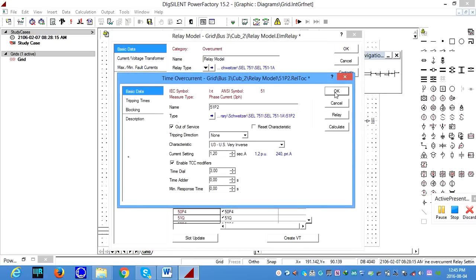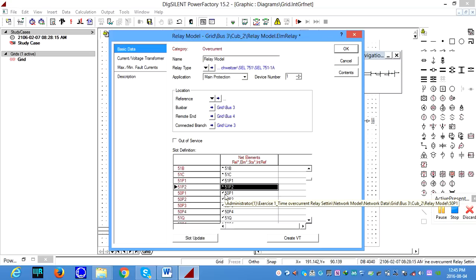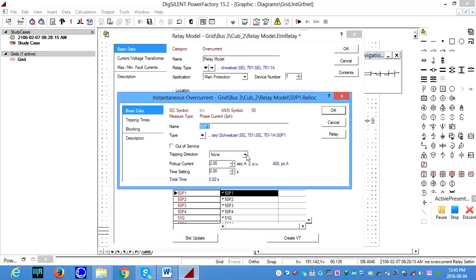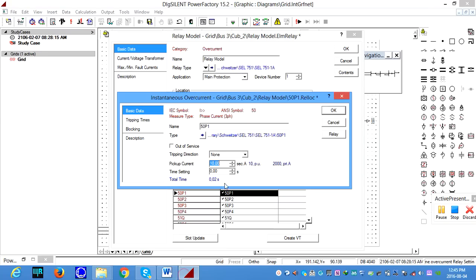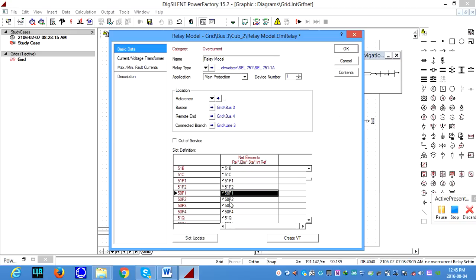Stage 2 is not active, out of service, and we also want to make sure of the definite element 50P1. According to the 50P1, direction is none. But what is 50P1? The current setting must be 10, okay, secondary ampere is 10. If you look at the manual, secondary ampere 50P1. This is your 50P1. Your current secondary is 10 amperes, and the time dial is 0.01. So your time dial is going to be 0.01, 10 amperes. This is 50P1. We are happy about that.